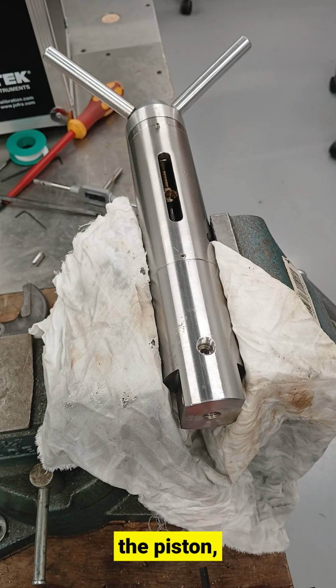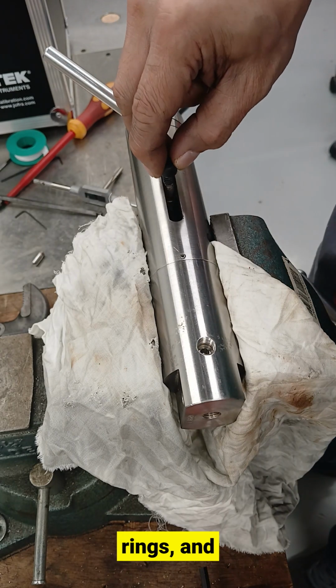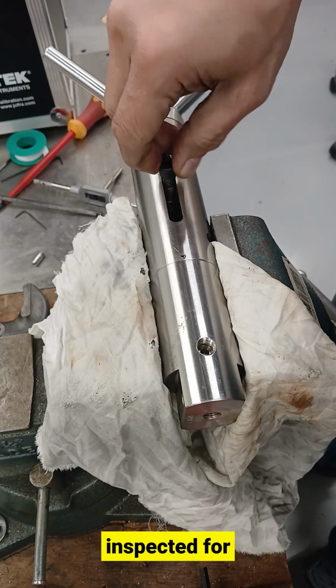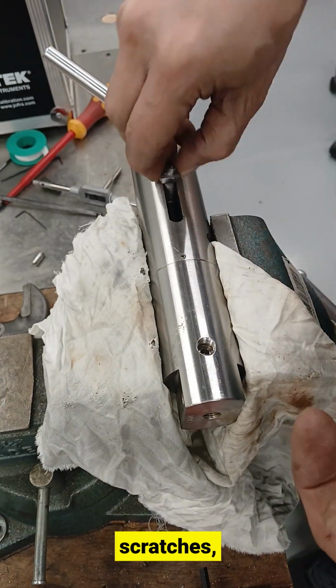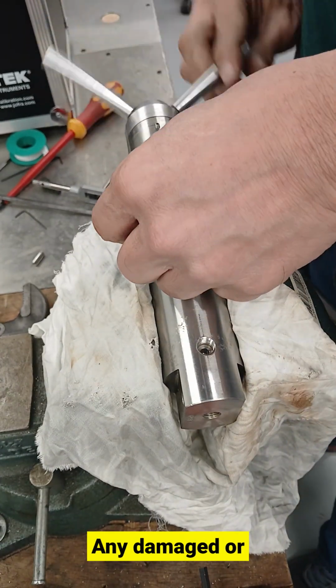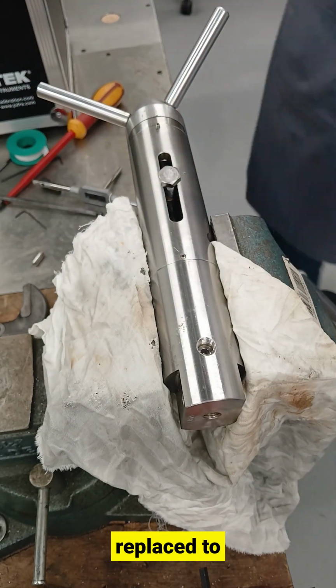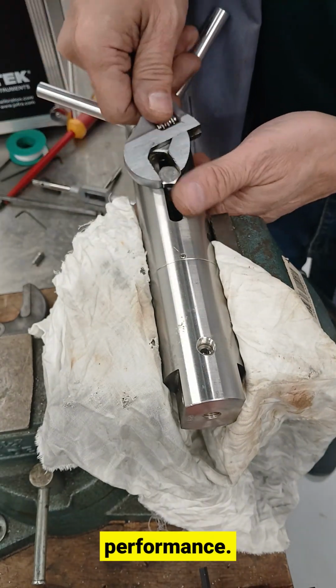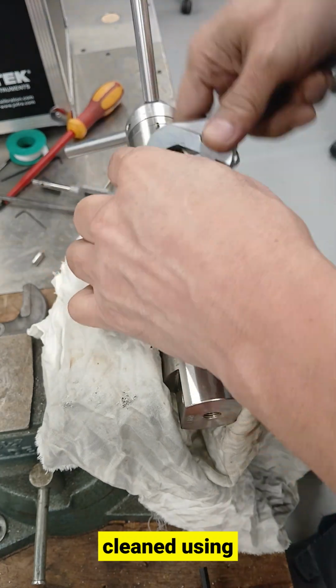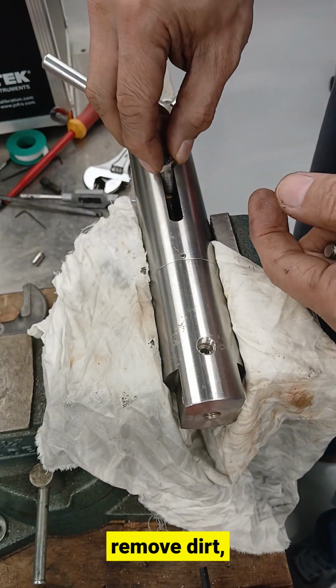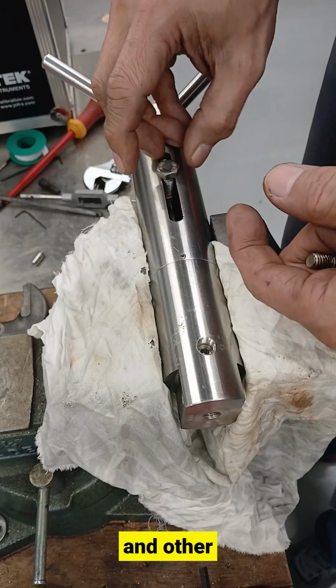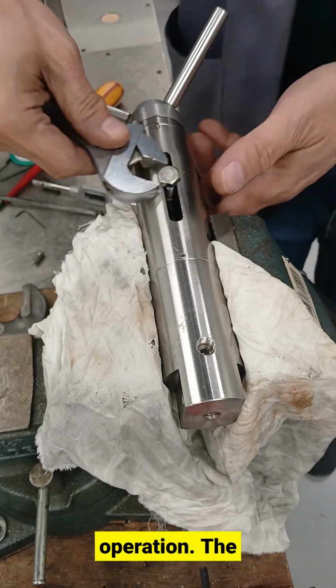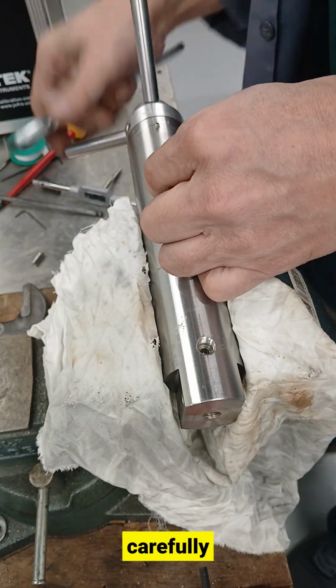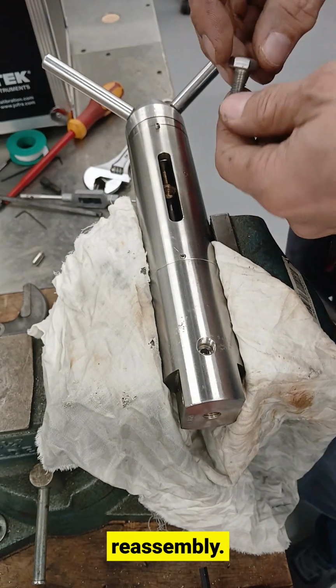Next, the piston, cylinder, seals, O-rings, and threaded components are thoroughly inspected for signs of wear, scratches, corrosion, or contamination. Any damaged or worn parts should be replaced to maintain the pump's performance. All components are then cleaned using approved cleaning materials to remove dirt, old lubricant, and other contaminants that could affect smooth operation. The internal surfaces are carefully wiped and inspected before reassembly.